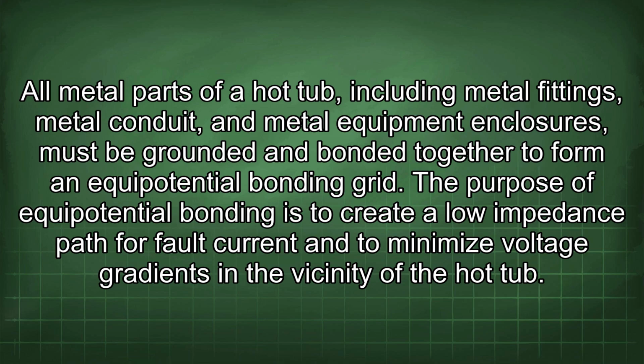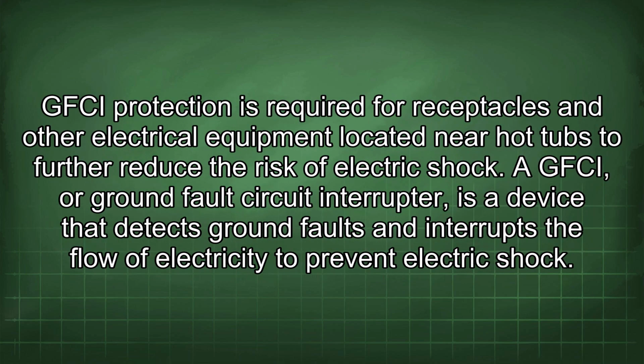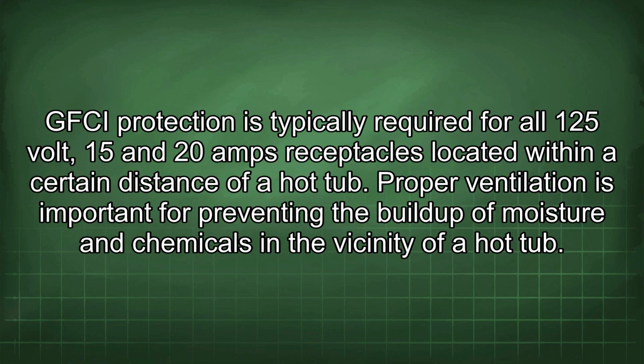The purpose of equipotential bonding is to create a low impedance path for fault current and to minimize voltage gradients in the vicinity of the hot tub. GFCI protection is required for receptacles and other electrical equipment located near hot tubs to further reduce the risk of electric shock. A GFCI, or ground fault circuit interrupter, is a device that detects ground faults and interrupts the flow of electricity to prevent electric shock. GFCI protection is typically required for all 125 volt, 15 and 20 amp receptacles located within a certain distance of a hot tub.